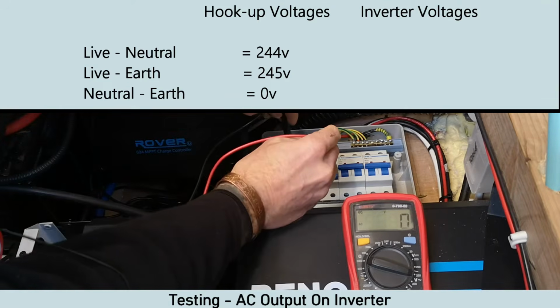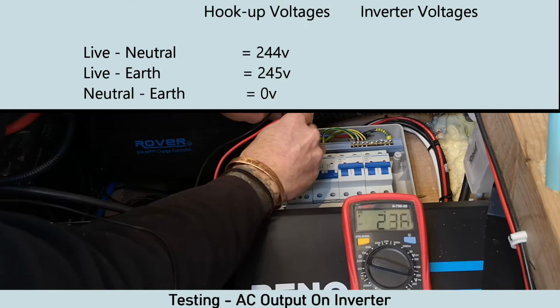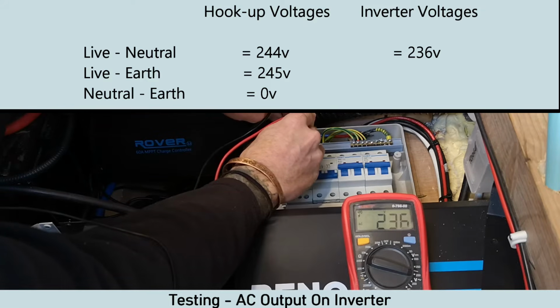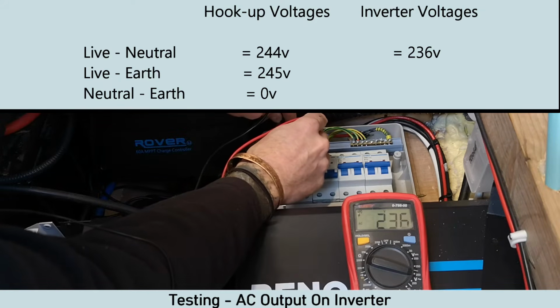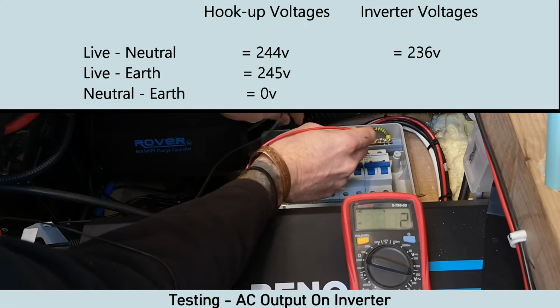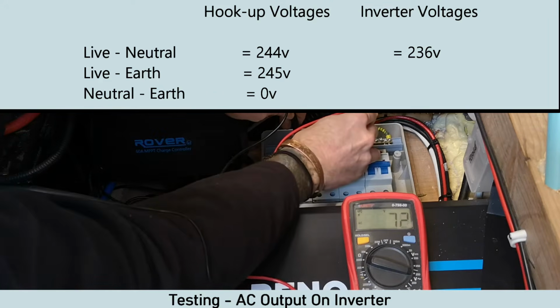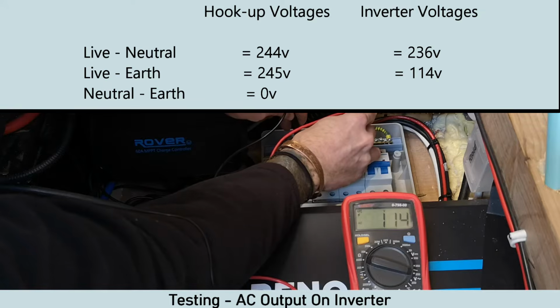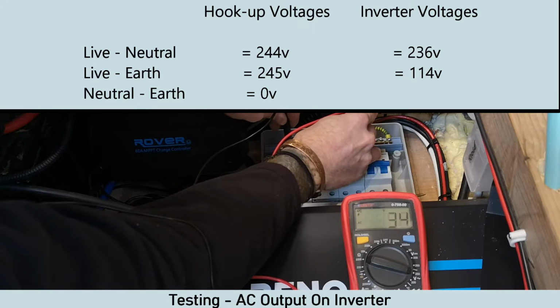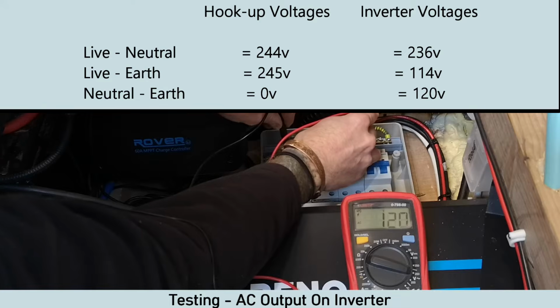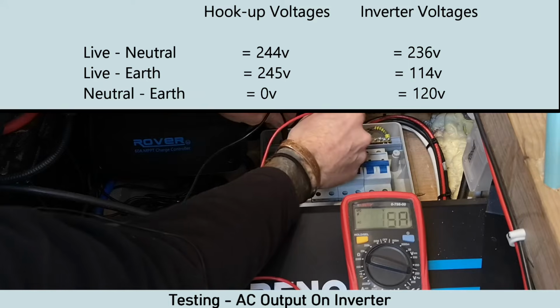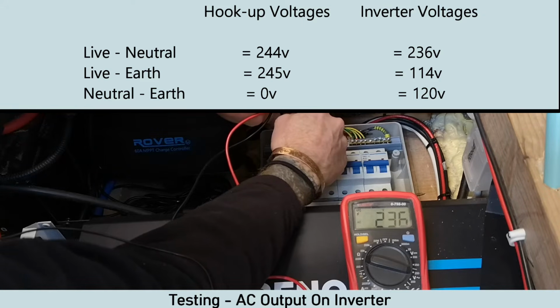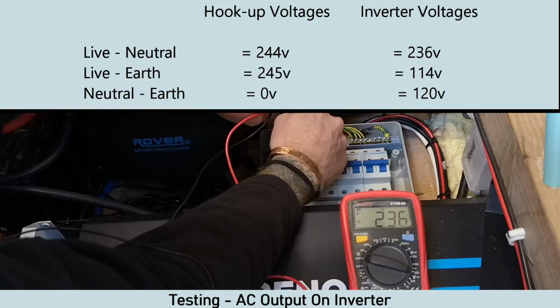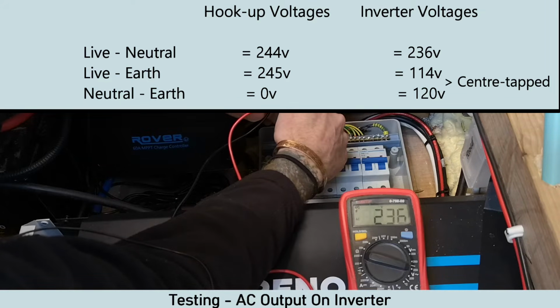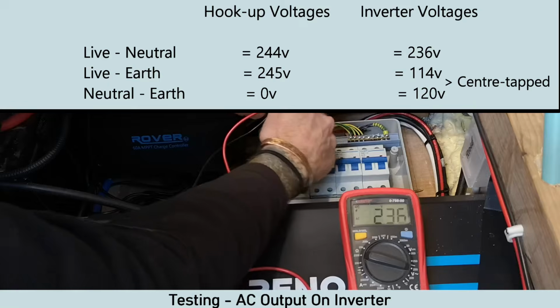So I'll go from live to neutral, which is giving me 236 volts. Happy days. So anything plugged in is going to work because it's getting 230. Now I'm going to go live to earth, 114 volts, and neutral to earth is 120 volts. So if you add those together, you're getting 234, so it should roughly equal your live and neutral, which is 236. So that just shows you that this inverter is center tapped.